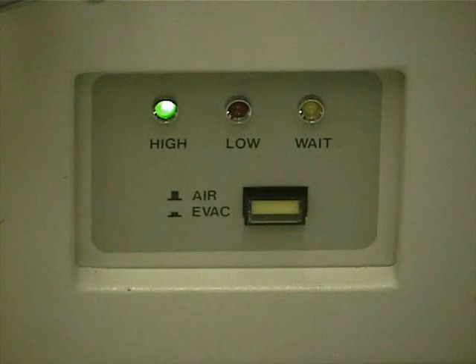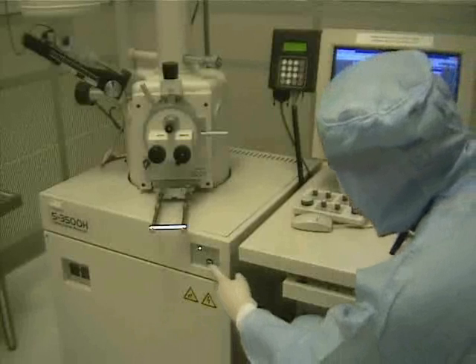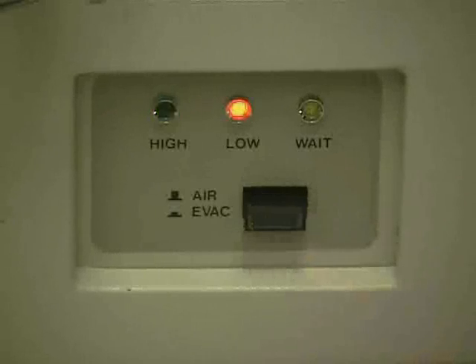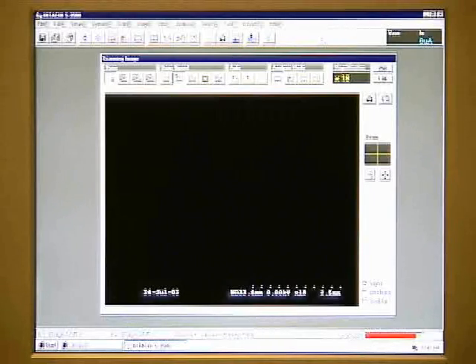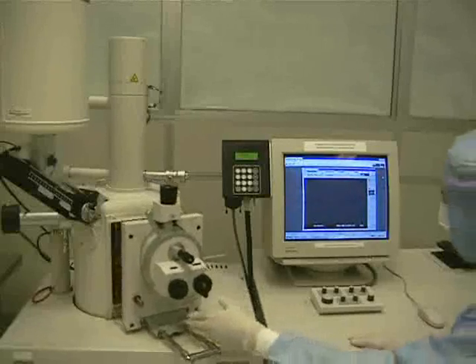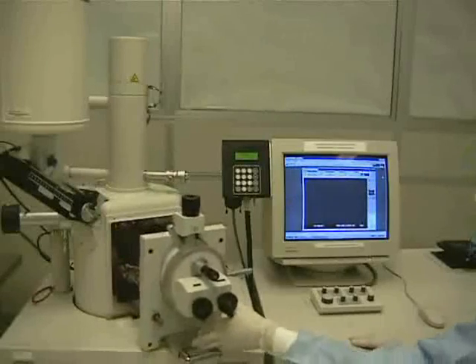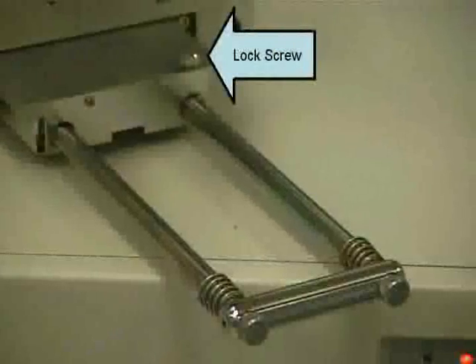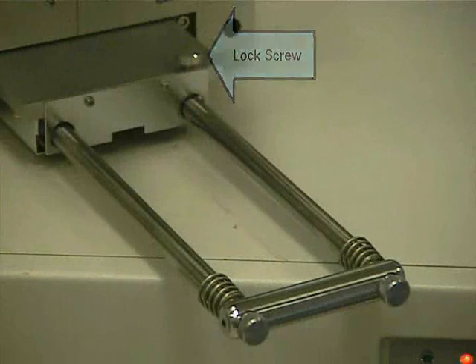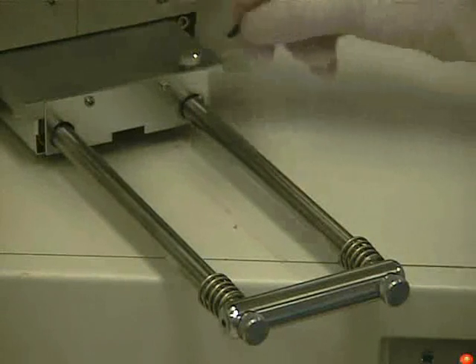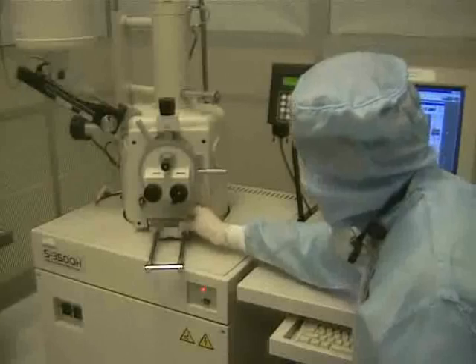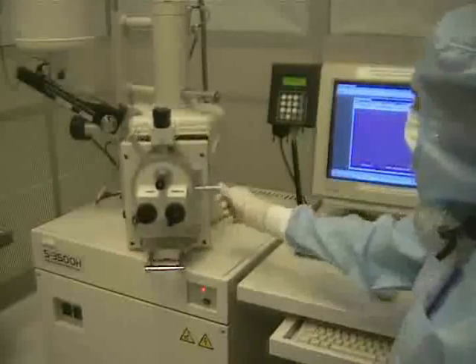Vent the chamber by pressing the evac off button on the front of the machine. After pressing the button, the red light will come on indicating that the chamber is now venting. It takes a few minutes for the chamber to vent. The bar on the software indicates when the chamber has been vented completely as well. The chamber door will open by itself when it reaches atmospheric pressure. If the software indicates the chamber being vented but it does not open, the lock screw located on the base of the chamber door might be tightened. Loosen the lock screw for the door to open.